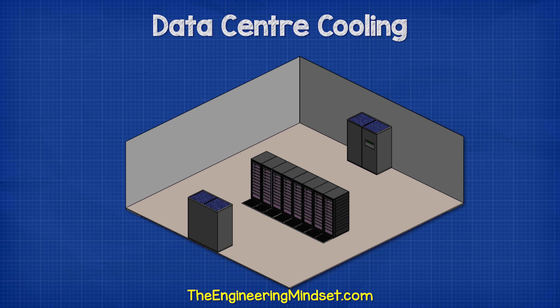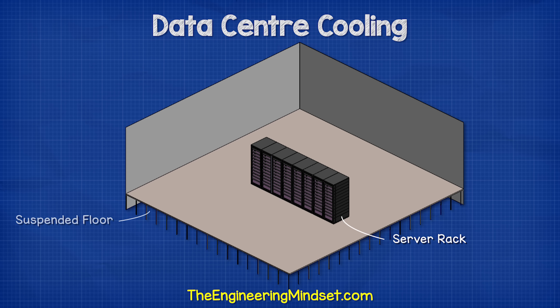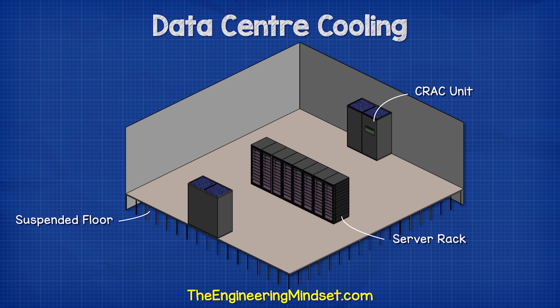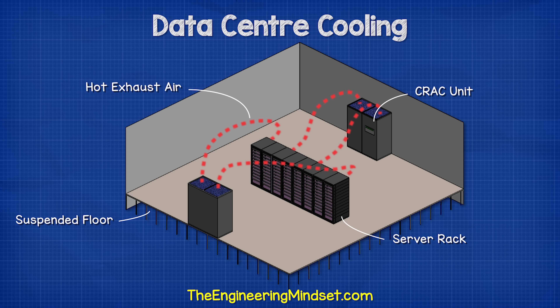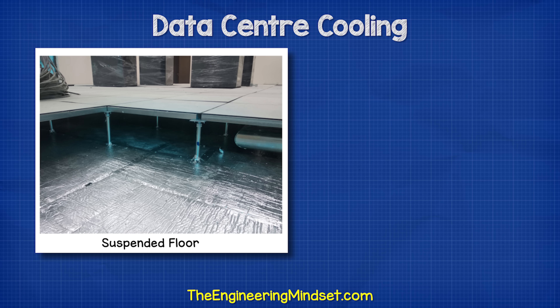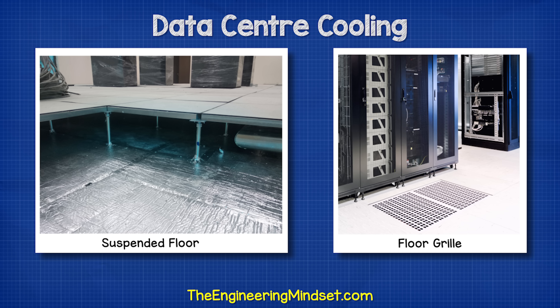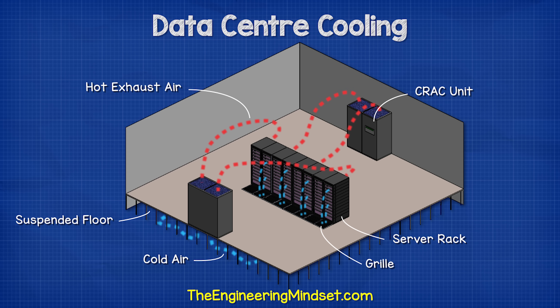If we look at a typical, simple data center, we find the server racks within the room and these are typically installed on a suspended floor. Around the perimeter of the room we find CRAC units, which stands for computer room air conditioners. These CRAC units suck in the hot exhaust air from the servers into the top, then cool this air down and push it into the void under the floor. The floor tiles are made from thick, solid materials which contain the air within the void. Some floor tiles have grills built into them, strategically placed near the servers so that the cold air can exit the void and be sucked directly into the servers.